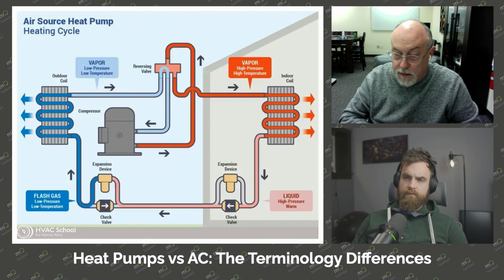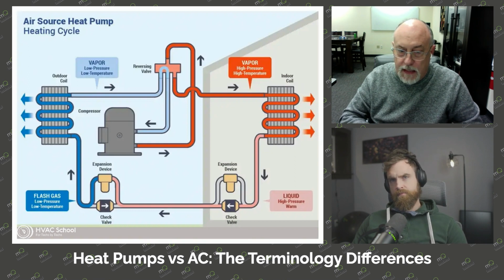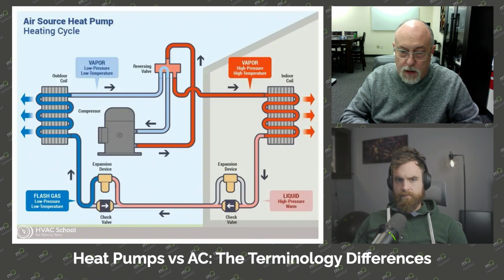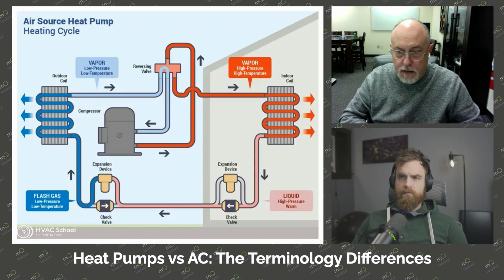But regardless, now in the heating mode, in measureQuick, we have to do some remapping, and then we do some different probe placement. First of all, we need to have a separate probe. Typically what we use for our discharge line, we'll remap to our vapor line. And that vapor line is going to be hot vapor that's going into the indoor coil. And then our suction line clamp will actually go on the true suction line. And sometimes it's hard to get to.